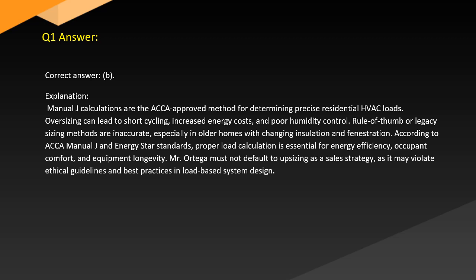Answer. Correct answer: B. Explanation. Manual J calculations are the approved method for determining precise residential HVAC loads. Oversizing can lead to short cycling, increased energy costs, and poor humidity control. Rule of thumb or legacy sizing methods are inaccurate, especially in older homes with changing insulation and fenestration. According to ACCA Manual J and Energy Star standards, proper load calculation is essential for energy efficiency, occupant comfort, and equipment longevity. Mr. Ortega must not default to upsizing as a sales strategy, as it may violate ethical guidelines and best practices in load-based system design.